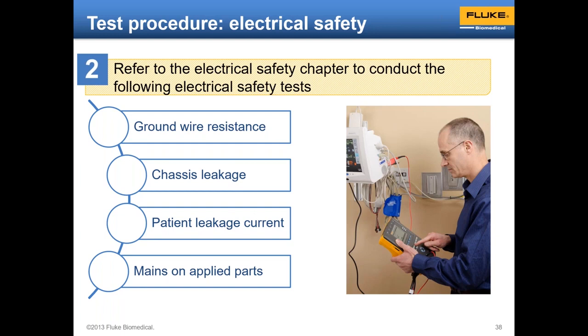And then we will do the patient leakage current test. That is the patient applied parts leakage current. Those patient connections that are continuously conductive from the medical device, the patient monitor in this case, all the way to where they actually touch or go into the patient. And the mains on applied part test with 100% of mains power applied to each patient applied part type grouping altogether. Okay, those are the tests that will be done.